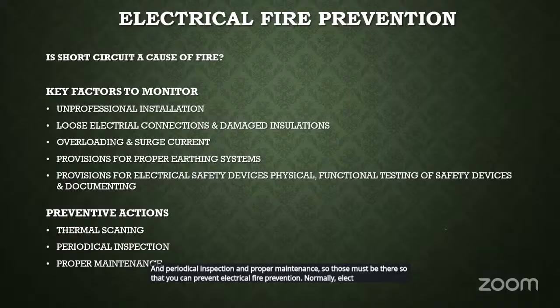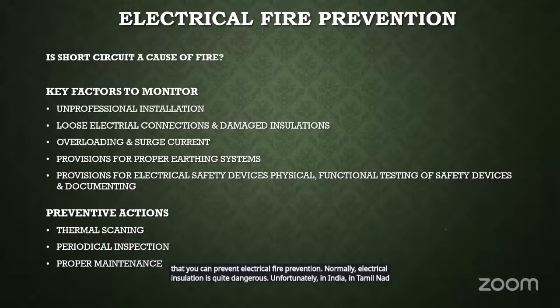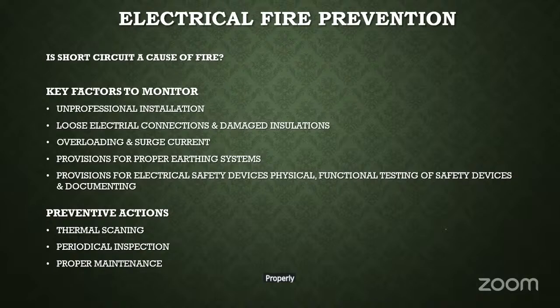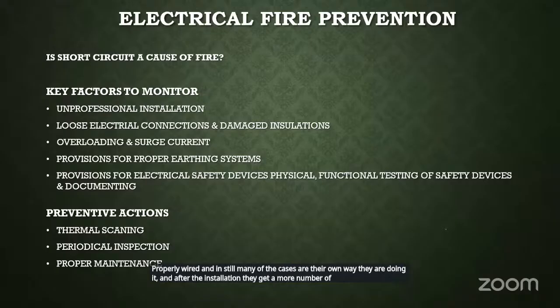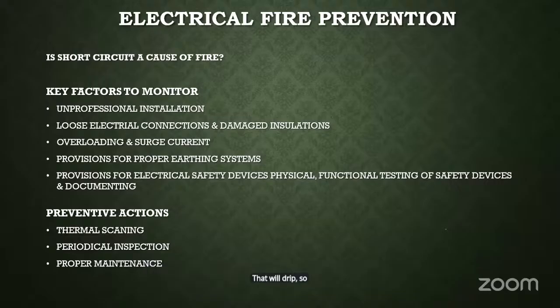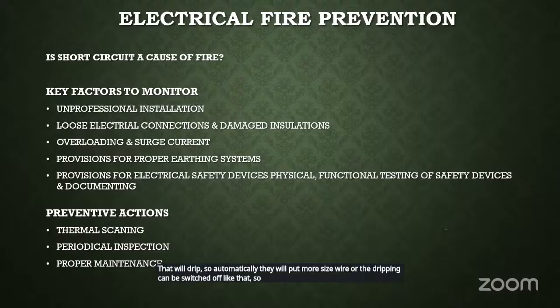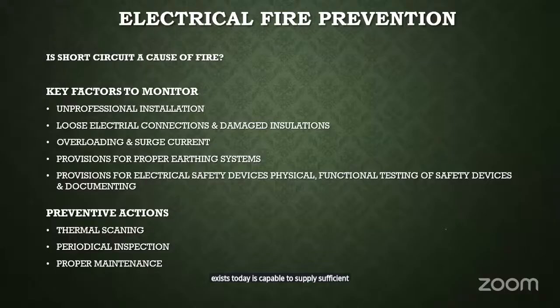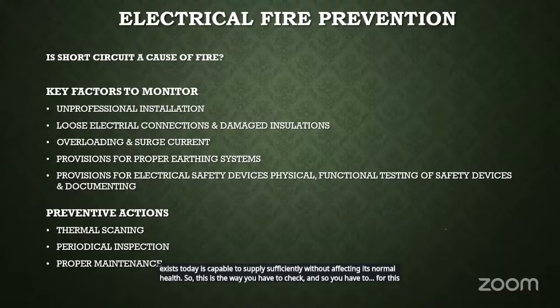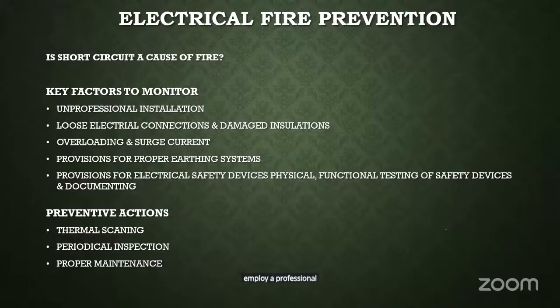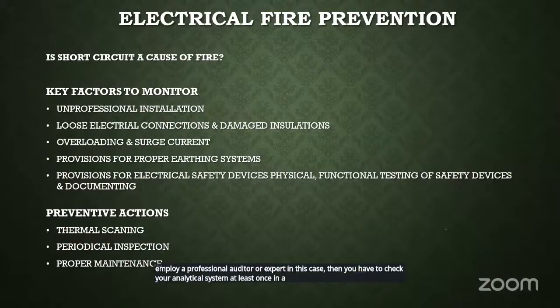Normally, electrical installation is quite dangerous. Unfortunately, in India, in Tamil Nadu, electrical installation is not properly verified, properly wired and installed. In many cases they do it their own way, and after the installation they acquire more electrical and electronic equipment, so naturally they become overloaded. Then the fuses will trip, so automatically they will put in a larger wire, or the tripping can be switched off, and so the electrical fire is bound to happen. These are the things we must understand in practice. So we have to check whether our existing electrical system is capable of supplying sufficiently without affecting its normal health. For this purpose you have to employ a professional auditor or expert, and check your electrical system at least once a year. That's fine. Next, please.